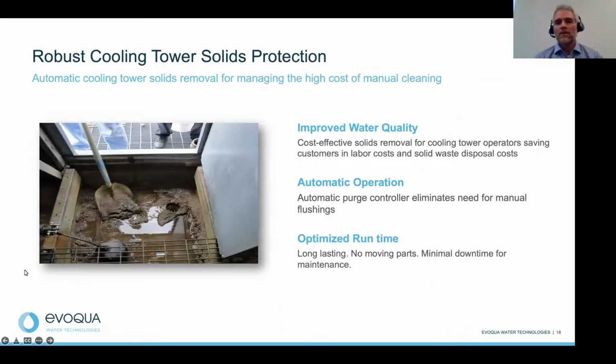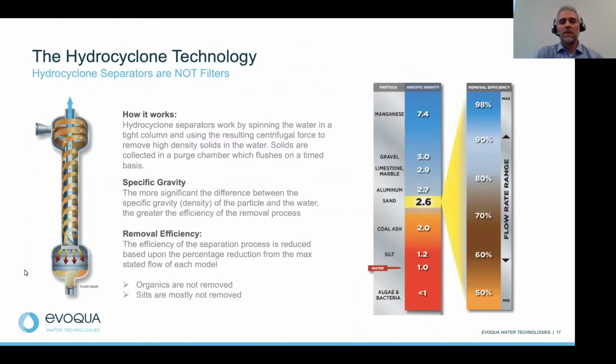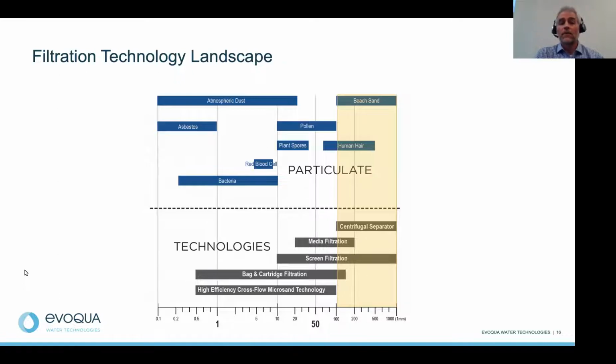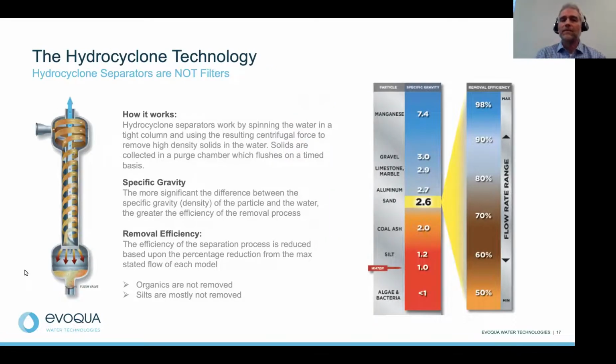Now let's look at how, again, this technology works. As I mentioned earlier, hydrocyclone separators are not filtration, but they are very good at separating very dense, heavy particles. The technology works by injecting a high velocity flow tangentially into a vessel, creating a centrifugal force. That centrifugal force acts as a pull and separation of high dense particles. So the greater the variation between water's gravity and your particulate's specific gravity, the better efficiency of separation you'll have in that cooling environment. So this technology is really good for particles that are greater than a specific gravity of 2.6 or higher. And anything that is less than that, you ultimately have varying different efficacies.